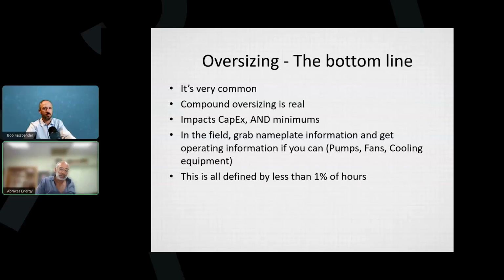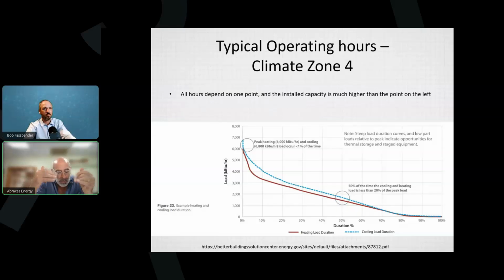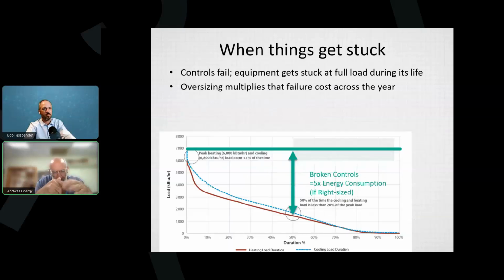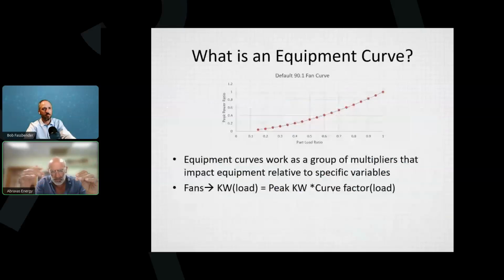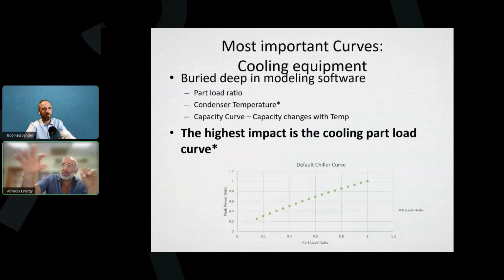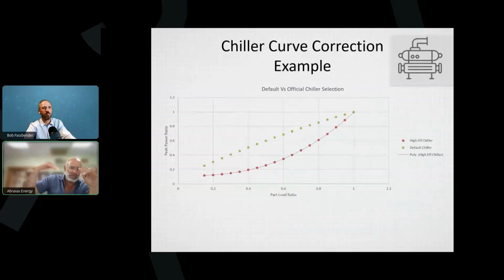Okay. Another question. So one thing I noticed, and people who have been attending all my webinars know I talk about this on occasion. There are these DOE-2 curves of chillers. And the DOE-2 curves of chillers, as far as I know, and I could be wrong, say that if the chiller is at, look, I'm retired, so I don't remember everything, but the chiller is at 100% capacity, it's using, this is the kilowatts per ton or something like that, or percentage of input capacity. And if it's at 50%, it's using this percentage of input capacity. So we have a curve.